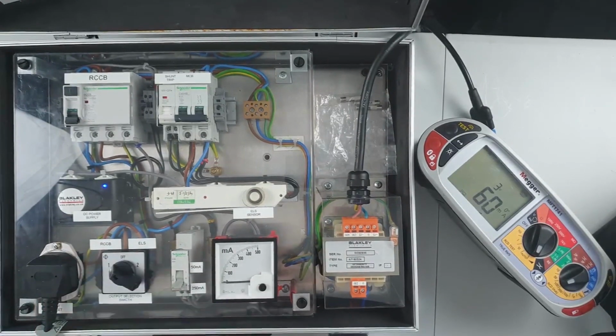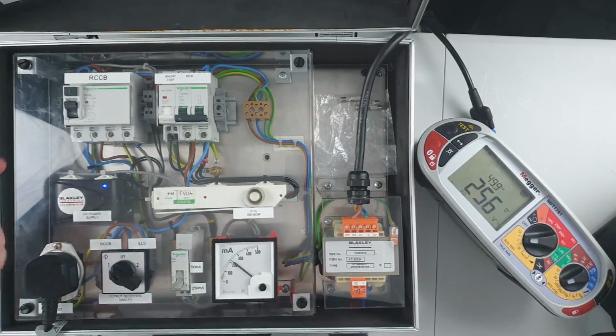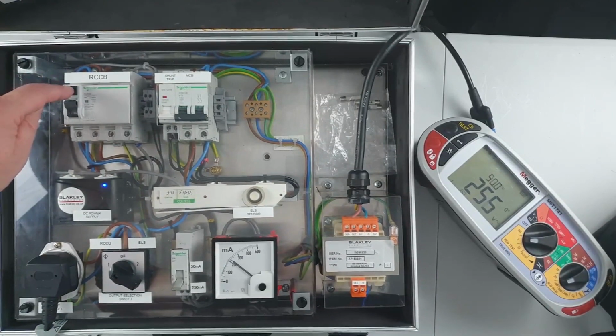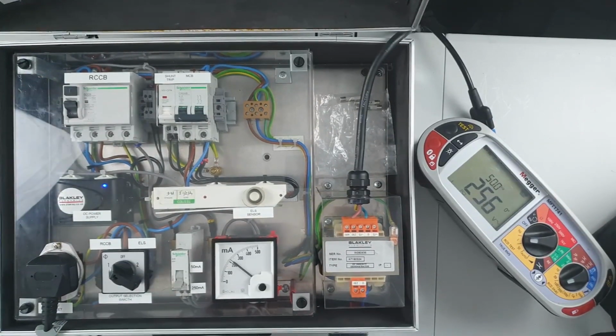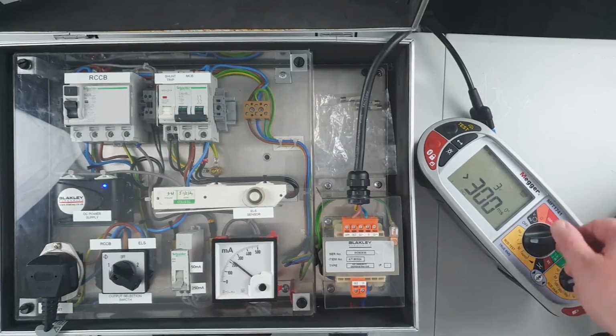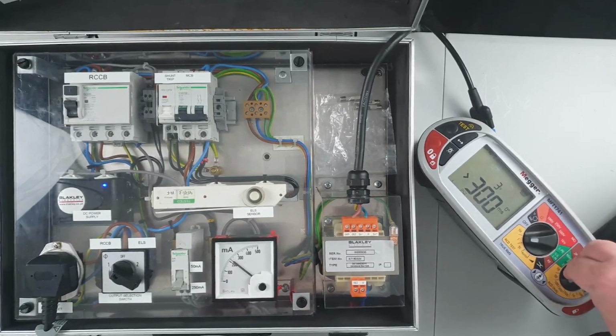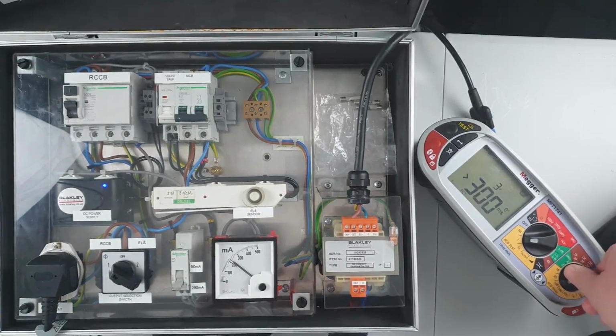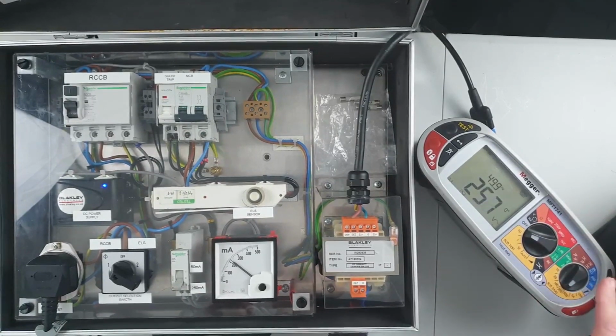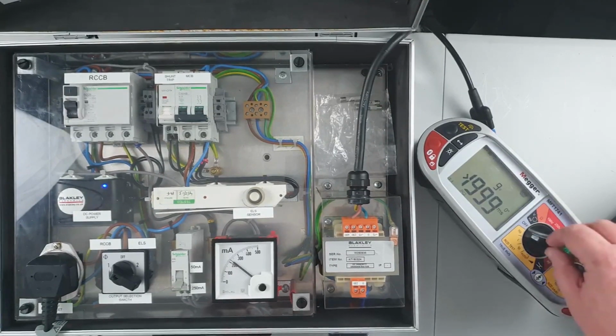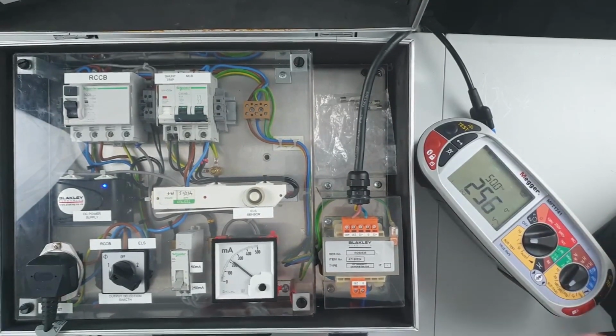Let's go up to 250. First thing to note now is at 250, it's so saturated that even the functional test isn't going to work. So the times one's not going to work. Neither is the times half or the times one at 100. So let's go with 300 times half, which is 150. Still doesn't trip. Let's step that up to times one, which is 300. Now it trips at 7.9. Okay, so 300 milliamp times one.